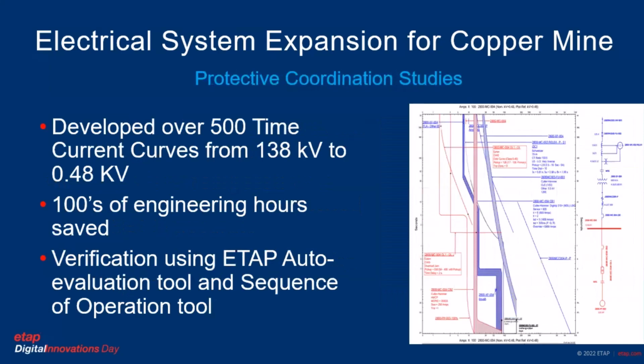Finally, we did the protection and coordination study. We developed about 500 time current curves from the levels of 138 kV down to 480 volts. Using the ETAP Star module, we developed all these TCC curves, and the detailed relay settings for the entire electrical system expansion were accomplished.